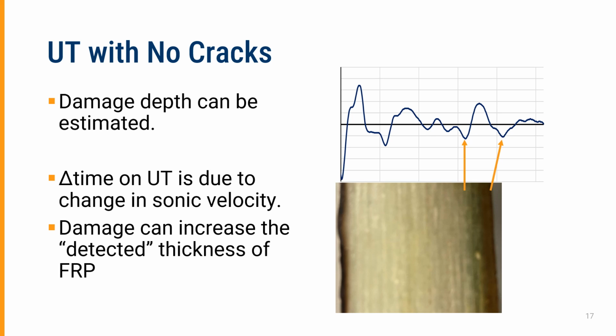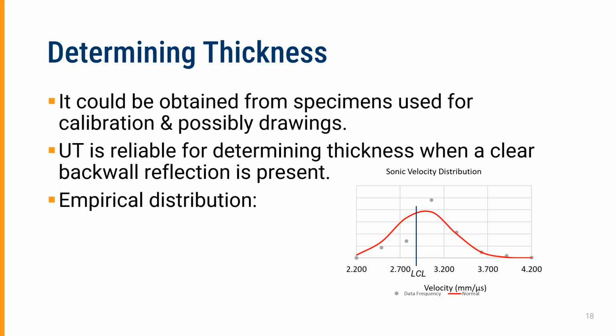Damage can actually increase the detected thickness of FRP. If you have a new thickness and a sonic velocity reference for new FRP, you may actually see the sonic velocity go down, or if you use the same sonic velocity, the thickness will increase. When it comes to determining thickness, we could actually use a conventional calibration sample like we do with steel or metal alloys. Drawings may actually provide some useful information on thickness, and recognize that thickness variations are allowed within most construction standards. Ultrasonic testing is reliable, however, for determining thickness when a clear backwall reflection is present. If we cannot get a clear backwall reflection, then there are other considerations, and we'll talk about those later in this presentation.